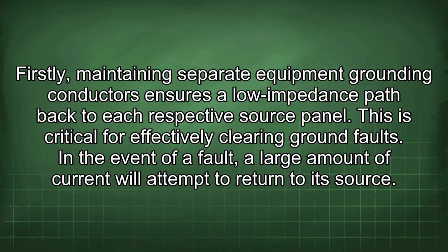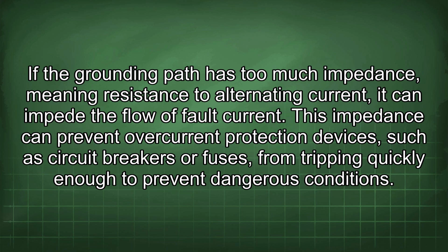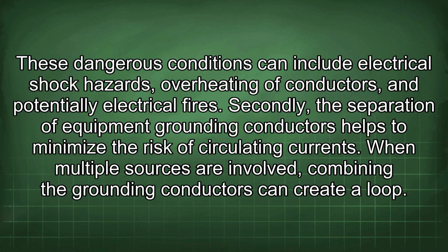In the event of a fault, a large amount of current will attempt to return to its source. If the grounding path has too much impedance, meaning resistance to alternating current, it can impede the flow of fault current. This impedance can prevent overcurrent protection devices, such as circuit breakers or fuses, from tripping quickly enough to prevent dangerous conditions. These dangerous conditions can include electrical shock hazards, overheating of conductors, and potentially electrical fires.